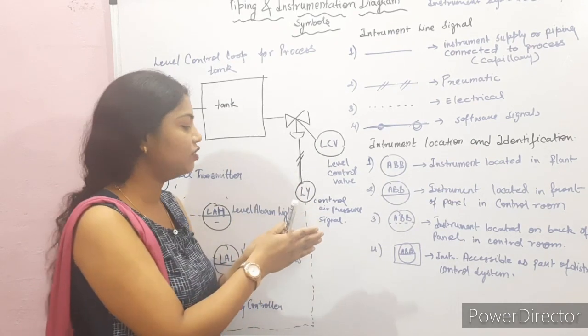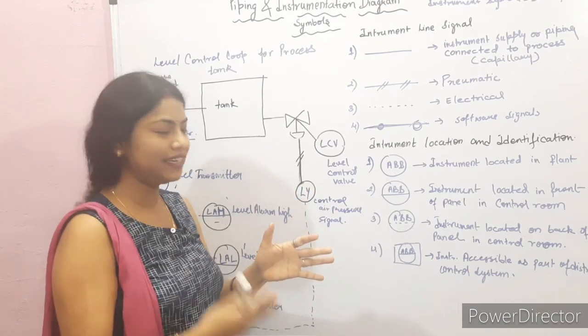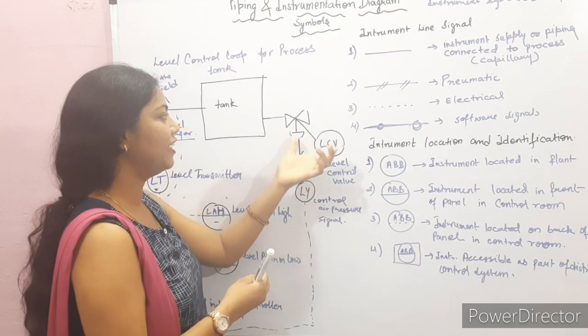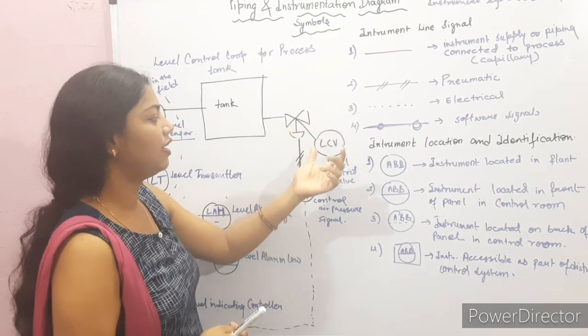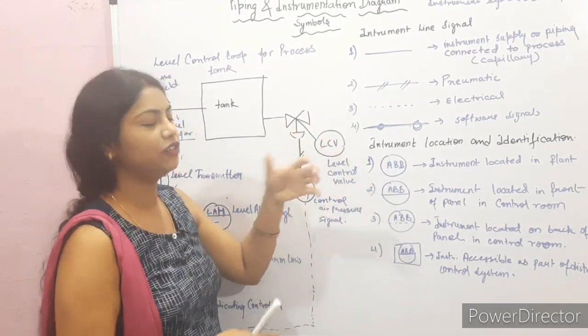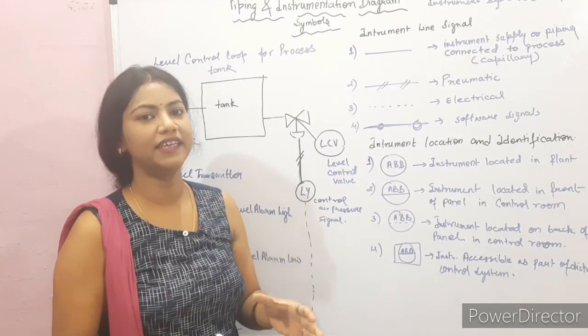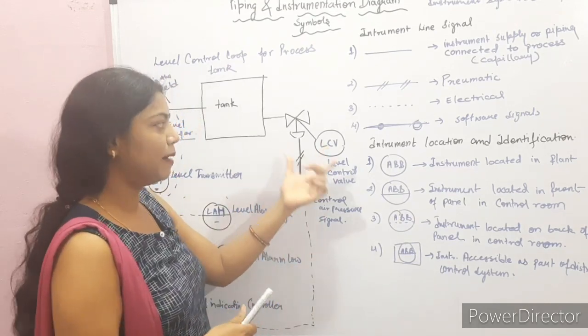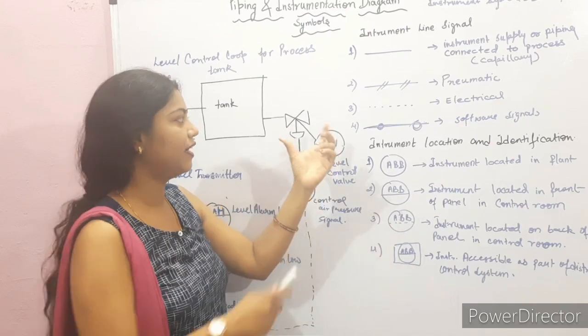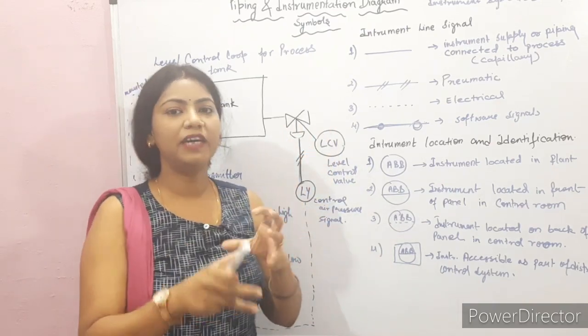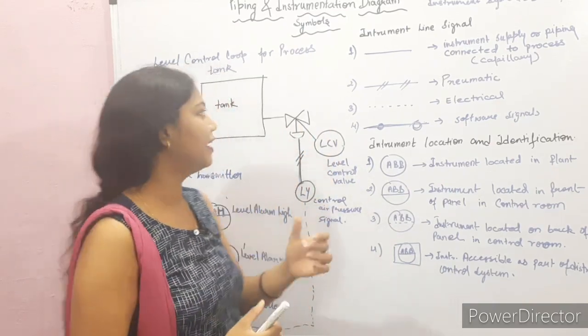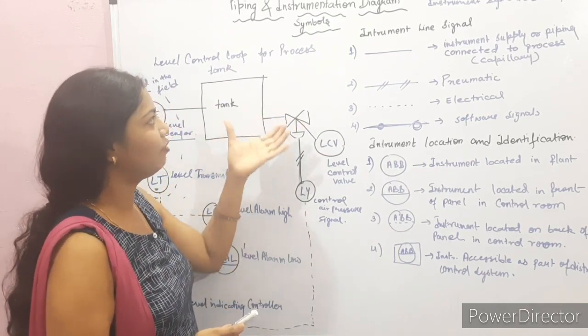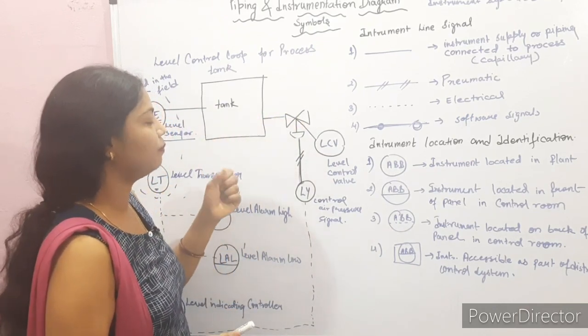The control signal — an air pressure signal — is sent through pneumatic lines to the level control valve. Then there is a comparison between the set point and the measured level. After comparison, the valve will open or close by a particular amount to maintain the level in the tank according to the set point.